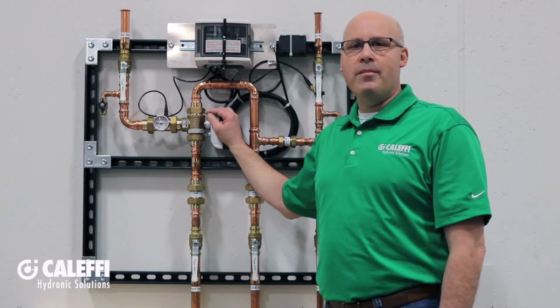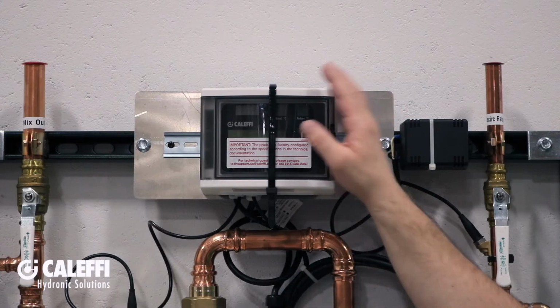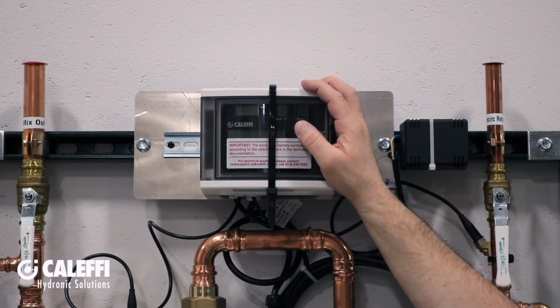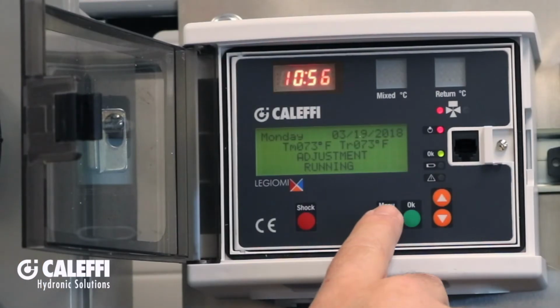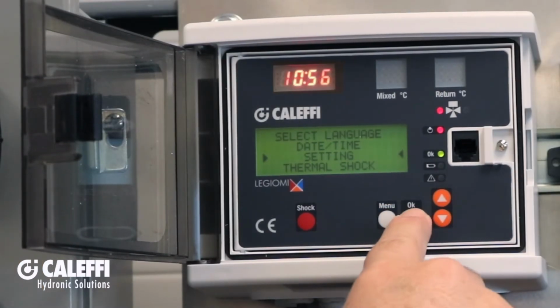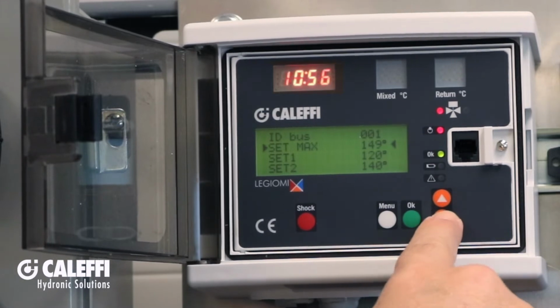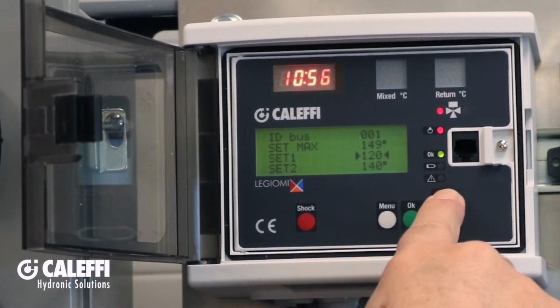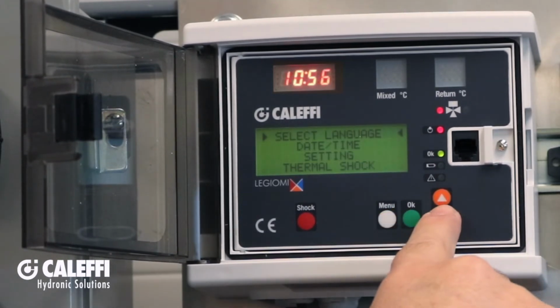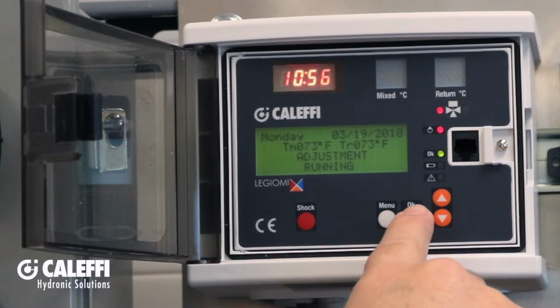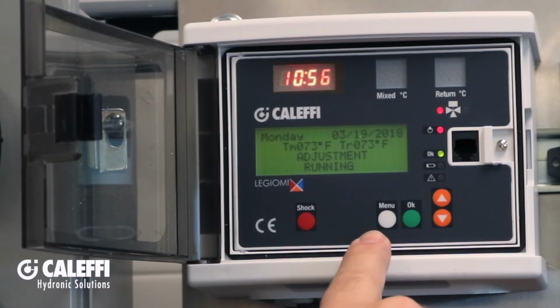Now let's look at it component by component. The brains of the assembly is this full-function user interface controller. It displays mixed and return outlet temperatures, shows time, date, day, status, and any alarms. It has a battery-backed memory with 40 days worth of data. Everything you need for setup and daily use does not require a PC.